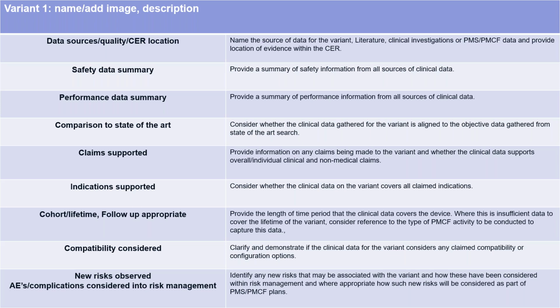And also think about compatibility. Whenever you claim compatibility to other devices, then obviously evidence and data needs to be provided. Sometimes that is technical data, but sometimes that is also clinical data, and consideration here about that variant and where its compatibility data is demonstrating that it is applicable to another type of device, for example.